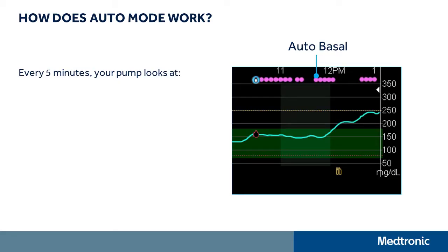You may be wondering, how does auto mode work? Well, the pump calculates and delivers insulin every 5 minutes. We call this insulin auto-basal, which are the pink dots at the top of your CGM graph, and the auto-basal is based on some key information. Your sensor glucose reading and its trend. The pump takes into account not only what your SG reading is, but also how fast it's moving and how long it's been away from your glucose target.